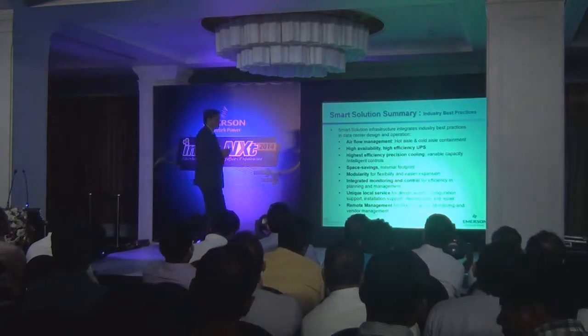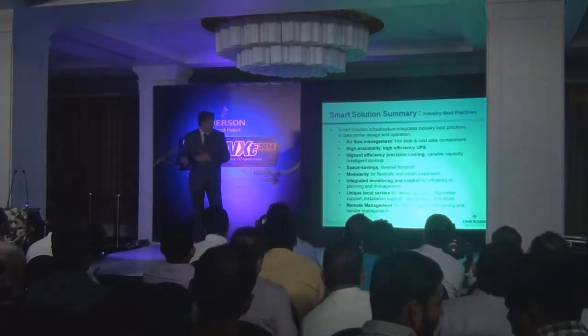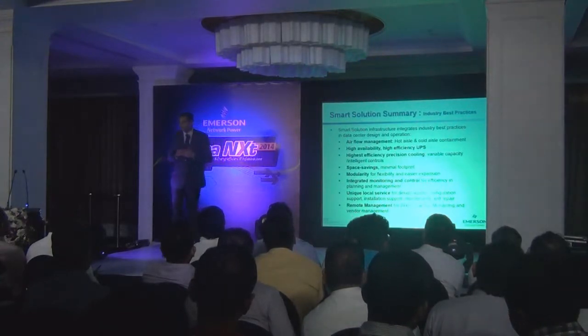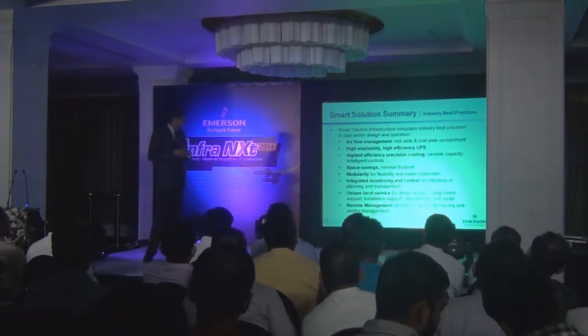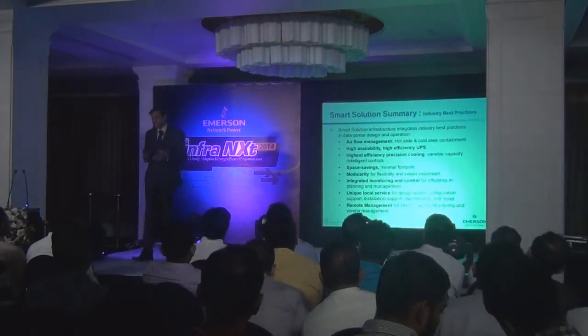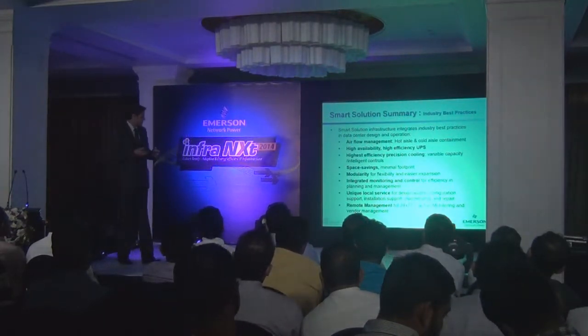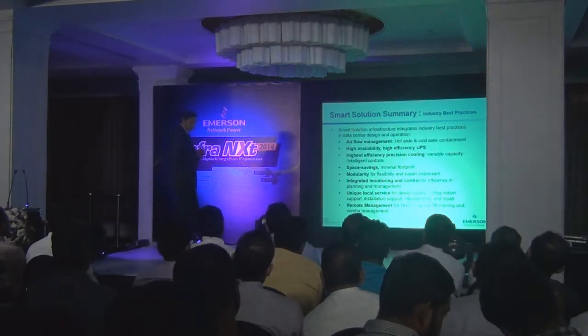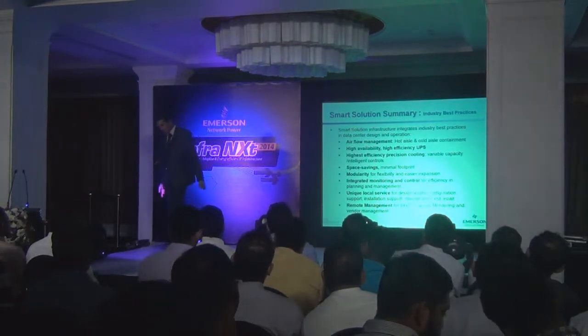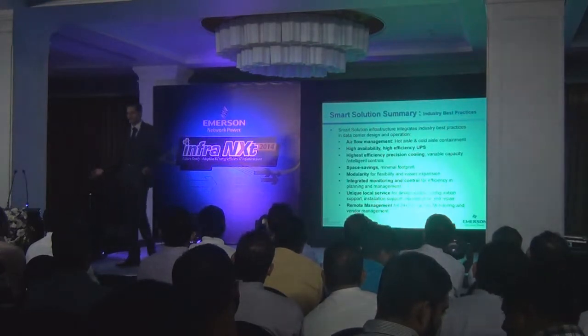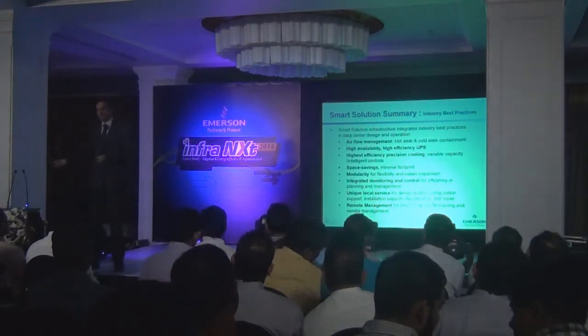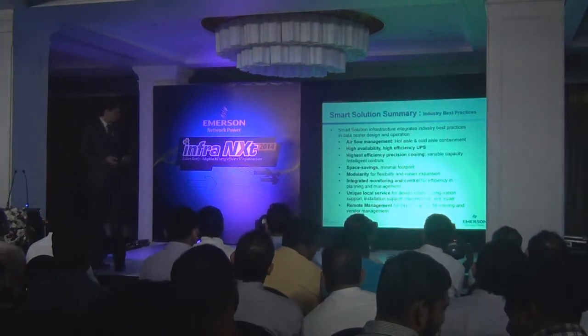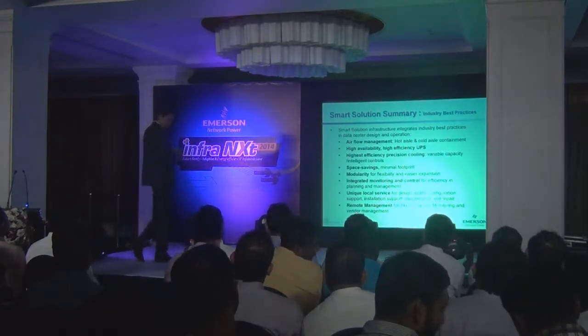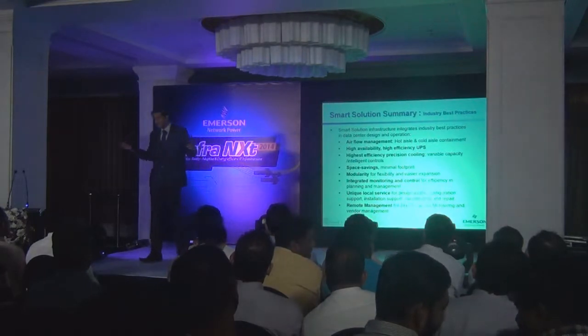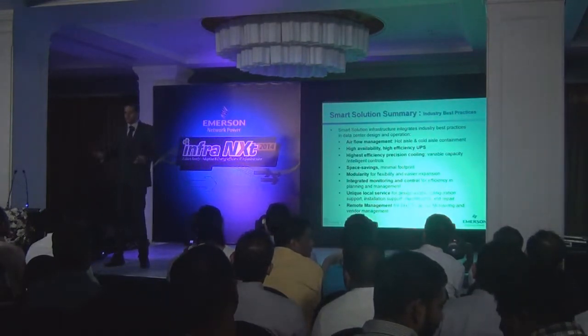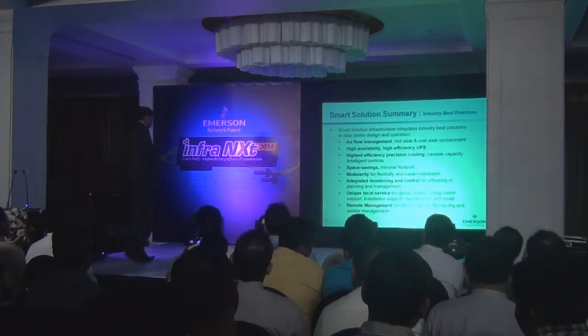We achieve that by following a similar concept of airflow management with hot and cold air, high availability and high efficiency UPS, and the highest efficiency precision cooling like CRV, which is the best precision cooling available in the market. It's space-saving too, a smart row of up to 6 racks can handle a data center that would otherwise need 1,000 square feet, saving a lot of space. It's also modular. If your requirement today is 6 kilowatt or 10 kilowatt, you can grow as your business grows, so that's the kind of solution we provide.